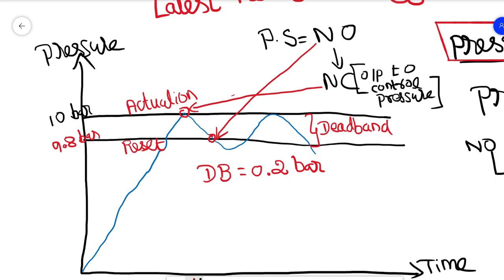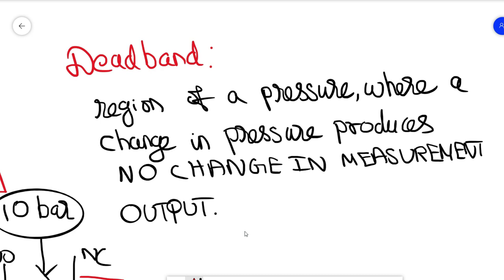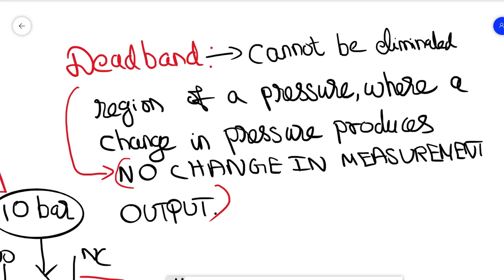So let's get to the definition again. So deadband is a region of pressure where a change in pressure produces no change in measurement output or control signal. All switches have this differential action, that is the deadband action, because it is inherent in any snap switch, right? The differential action of deadband cannot be eliminated.